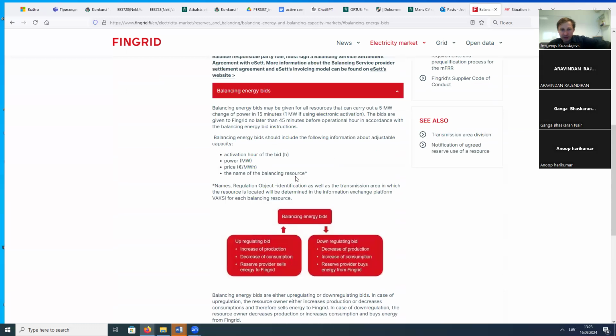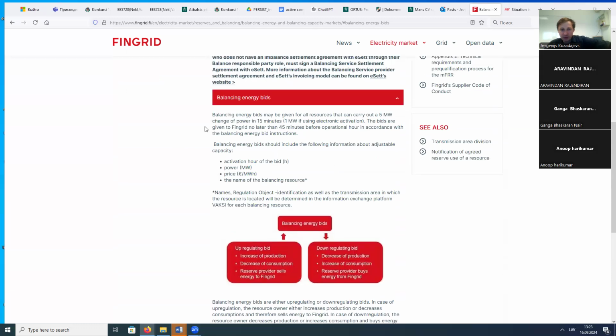Okay, and this is how it works. Balancing energy bids may be given for all resources that can carry out a 5 megawatt change in power in 15 minutes, or 1 megawatt if using electronic activation. The bids are given to Fingrid no later than 45 minutes before the operation hour, shown here as hour n, meaning 45 minutes before, according to the balancing energy bidding instructions.